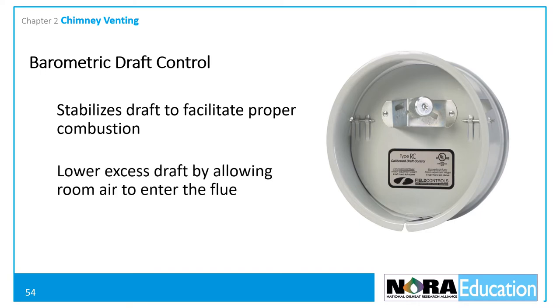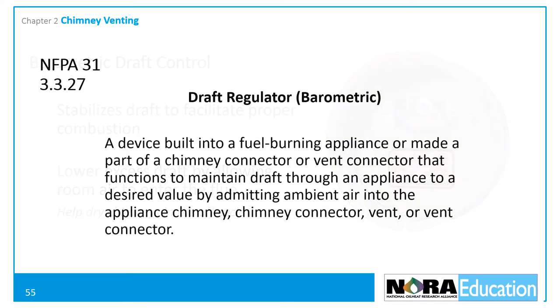Barometric draft controls lower draft by allowing room air to mix with the combustion gases as they rise through the flue pipe. They also help dry moisture from the chimney during the burners-off cycle. NFPA 31 defines the draft regulator as a device that functions to maintain draft through an appliance to a desired value by admitting ambient air to the appliance chimney, chimney connector, vent, or vent connector.